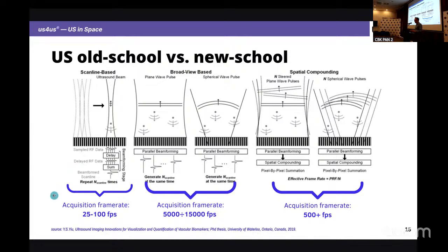So you can see that there are some limitations regarding frame rate, the number of images that you can really acquire and show. Those limitations are connected with the physics of ultrasound itself, the speed of sound: the ultrasound needs to go deep into the body, reflect, and go back, okay? If you multiply that by the number of scan lines, the number of beams that you need to cast, effectively you are reducing the frame rate. It is not a problem for imaging static objects, but for imaging a moving object like the heart, this is quite an important limitation.